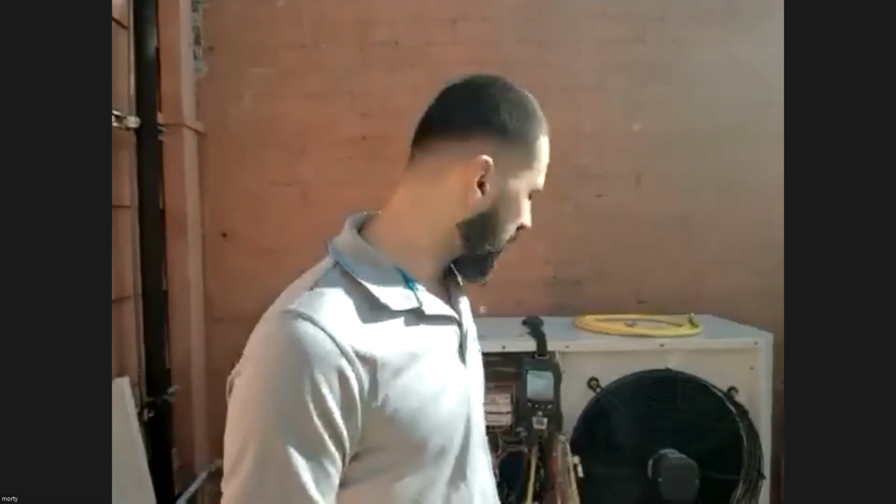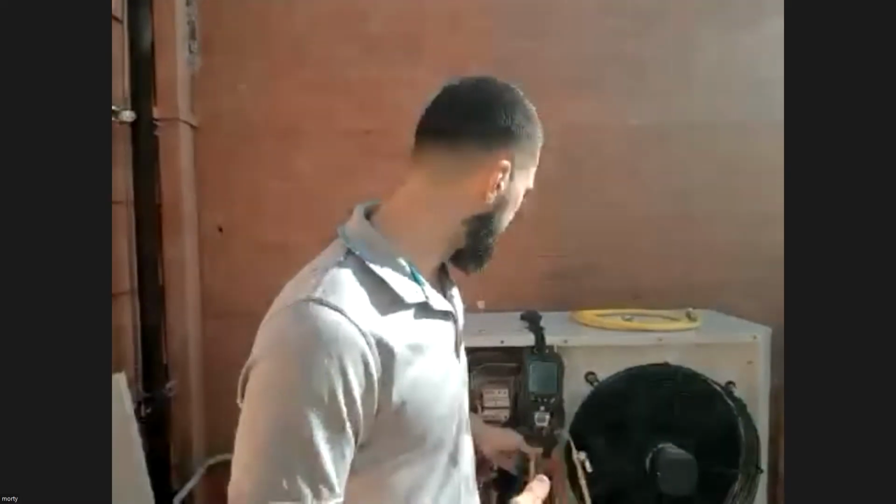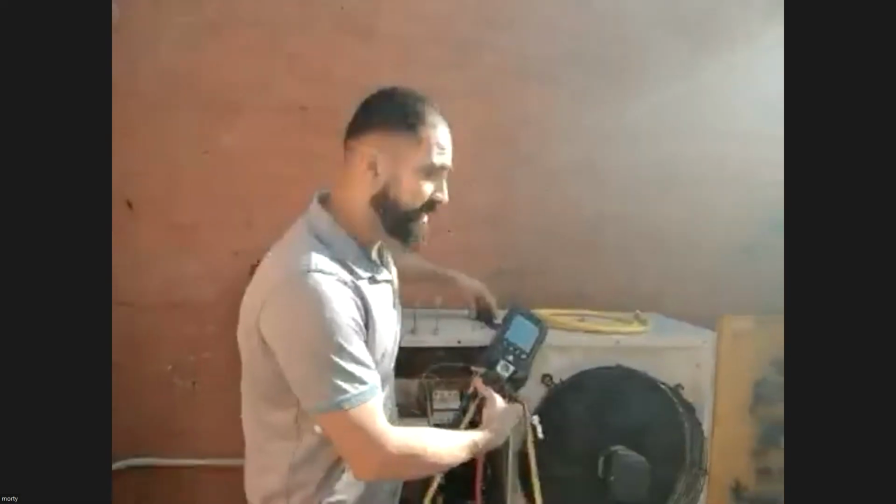Once again, if this sits in the sun for a long time, whether you've got a mechanical gauge or an electronic gauge, always give it about 5 to 10 minutes before you start reading, because sometimes it drops 0.2 of a bar, which is about 20 kPa. I work a lot in bars, I'm just not used to kPa. They are the same thing, just one decimal point between them.